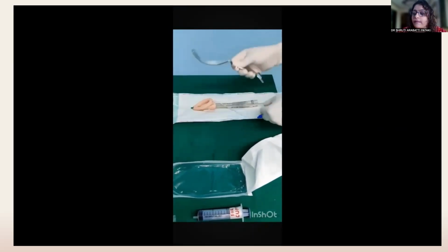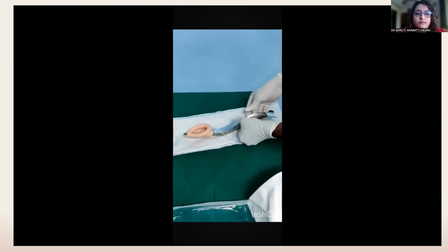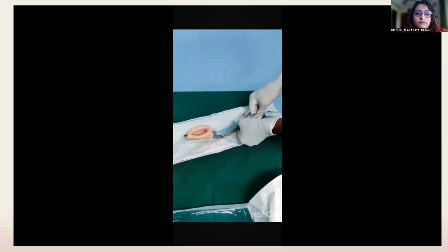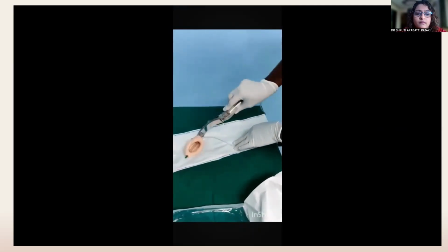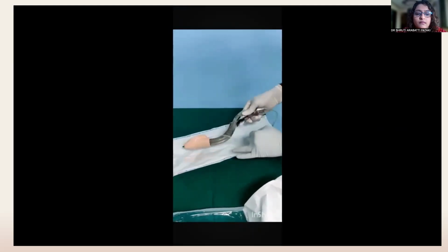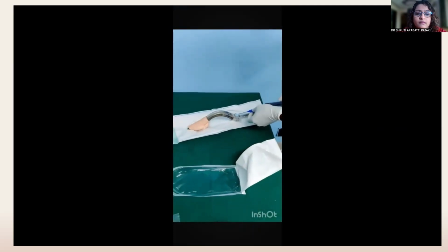Now place the metal introducer tip into the locating strap at the rear of the cuff. Fold the tubes around the convex surface of the blade and fit the proximal end of the tube into the matching slots of the introducer. Insert a syringe into the valve port of the inflation line.